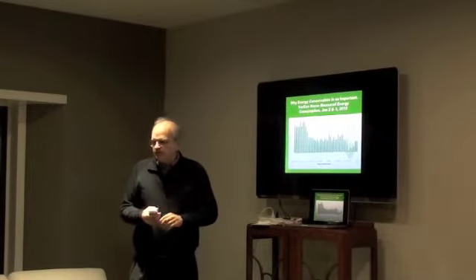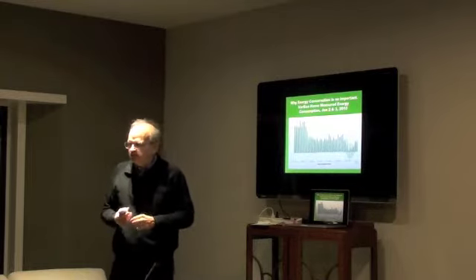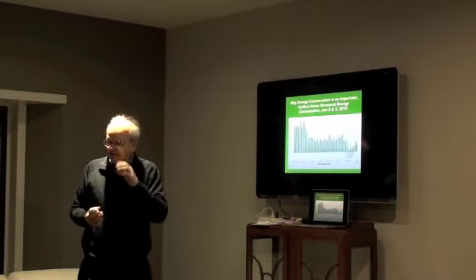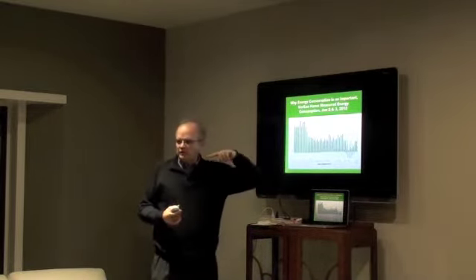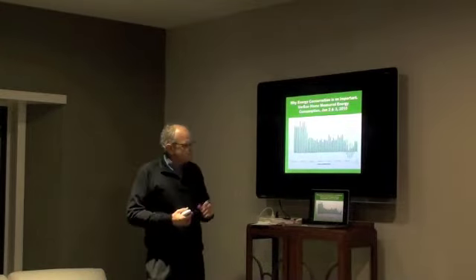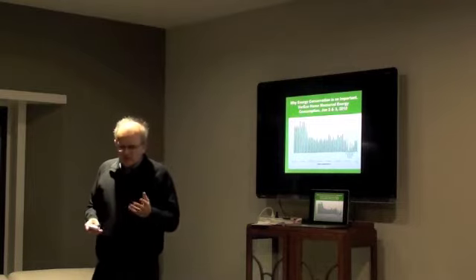How many of you know how big the furnace is in your house? Like how many BTUs per hour? 100,000 BTUs. Yeah, that's roughly 30 kilowatts of peak output. And this house is running around 2.5, and probably on the coldest day of the year it might be, say, 3.5 kilowatts. Generally they oversize furnaces somewhat as well, but definitely conservation comes first.